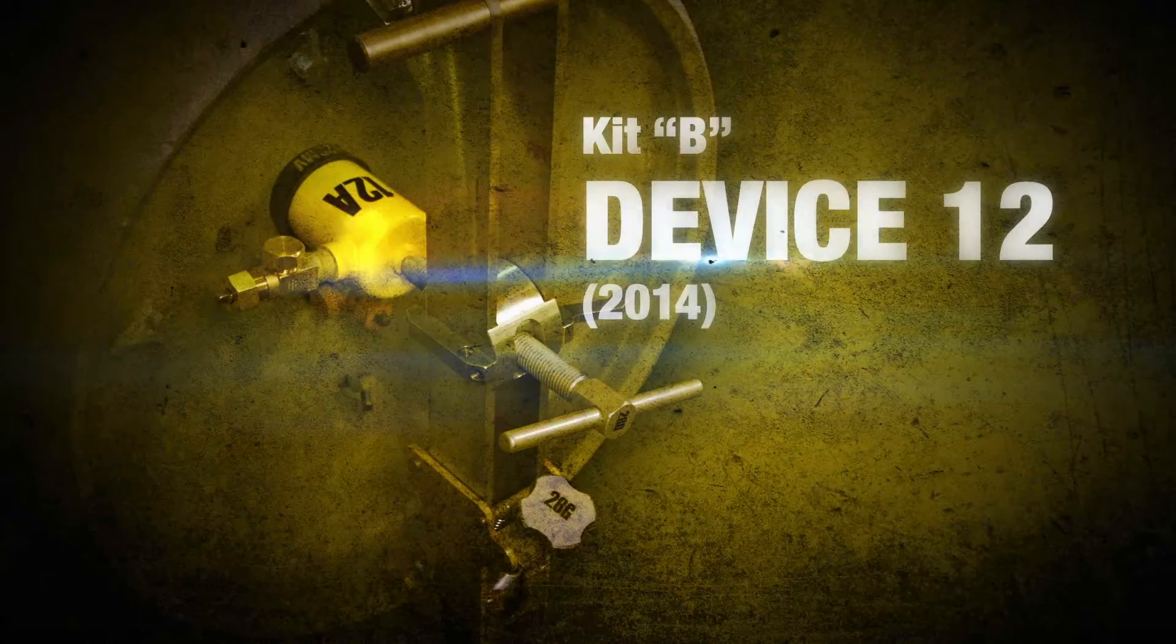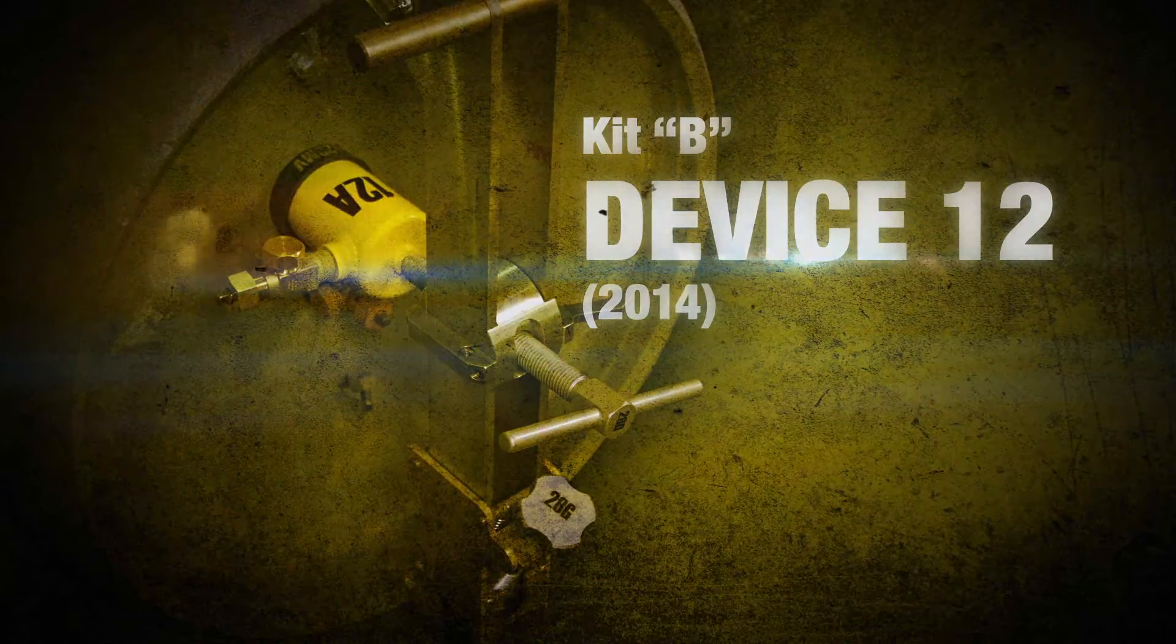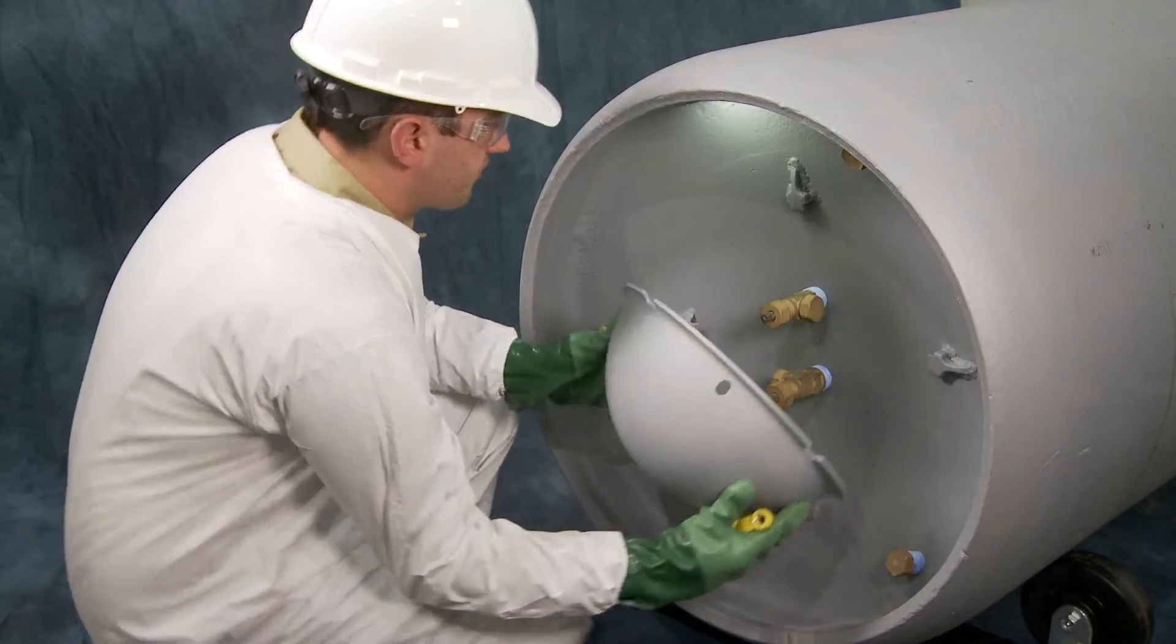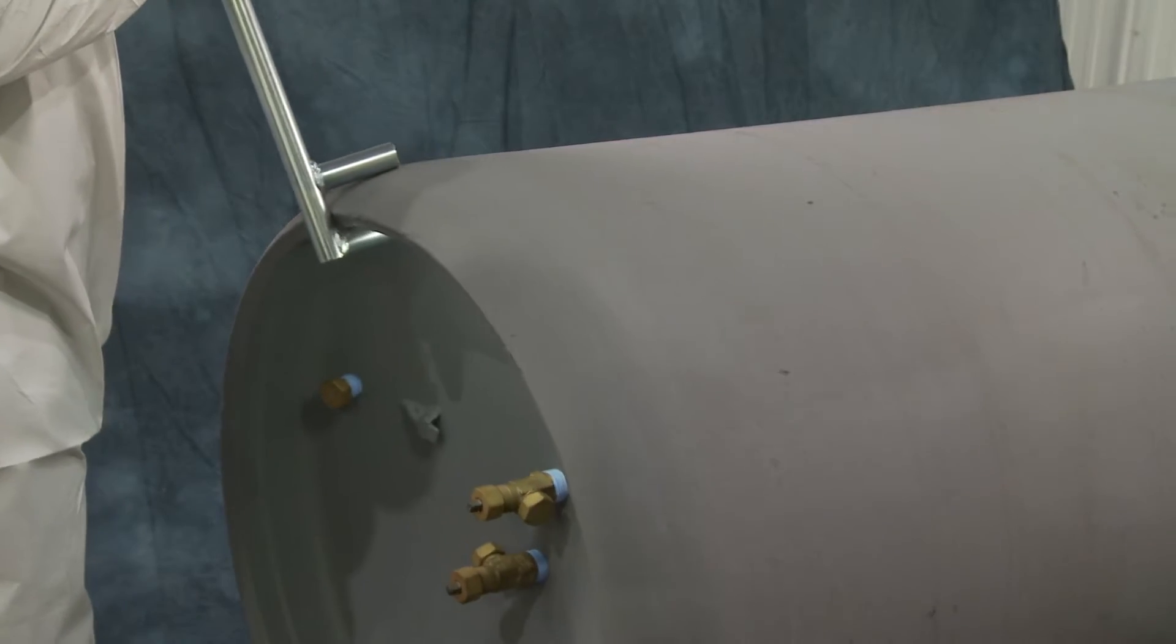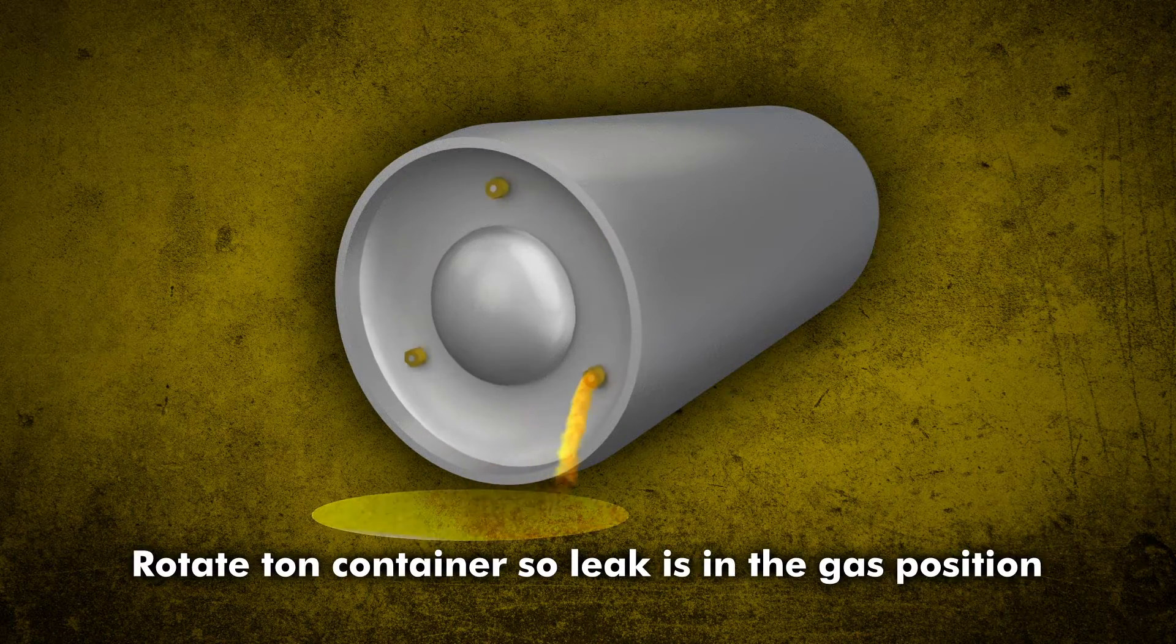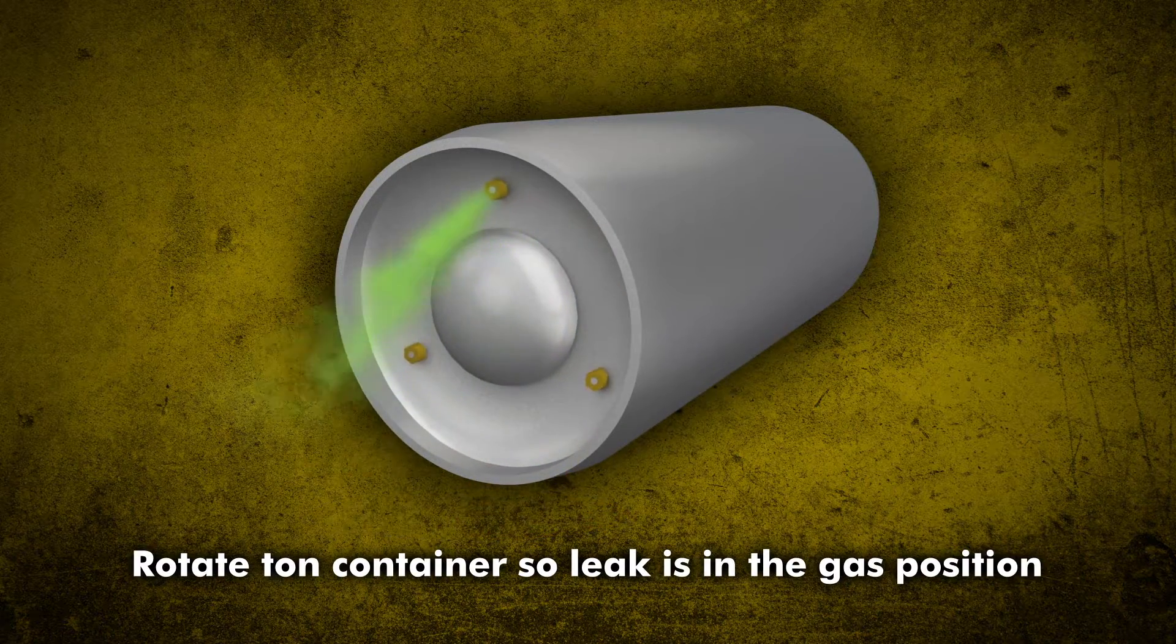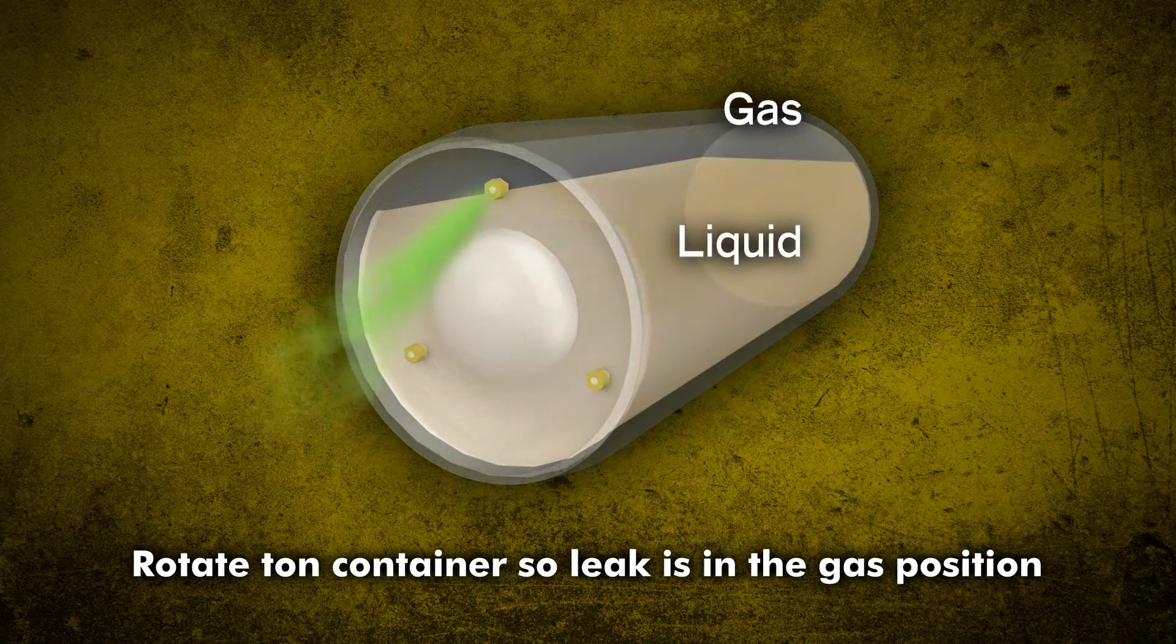Device 12 can be used to contain all leaks in and around the container valves. Remove the valve protective hood if in place and position the container so that the leaking valve is in the top or gas position. This results in a chlorine gas leak and not a liquid leak.